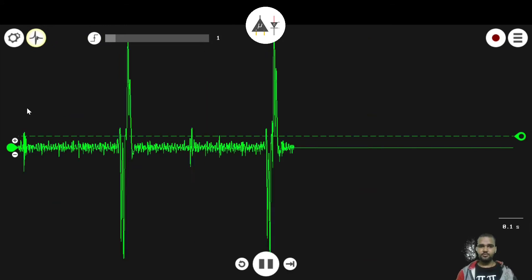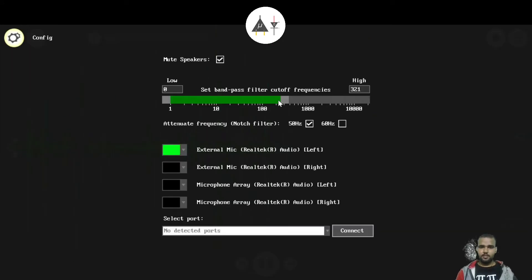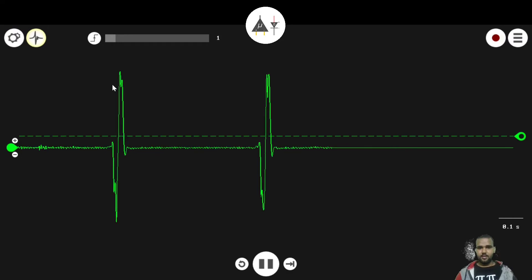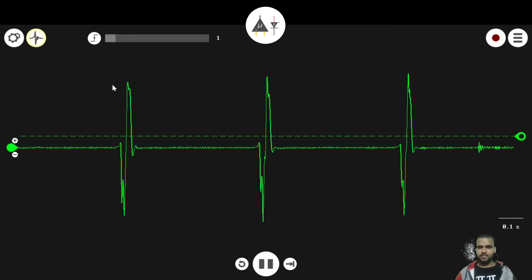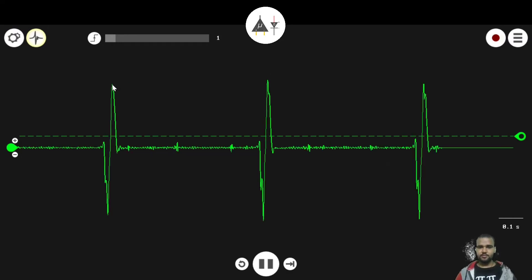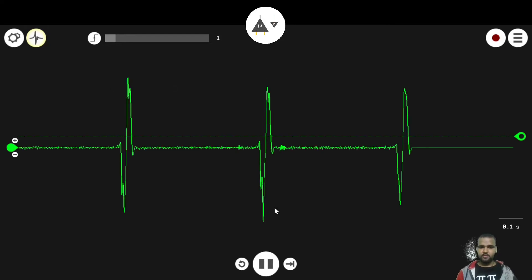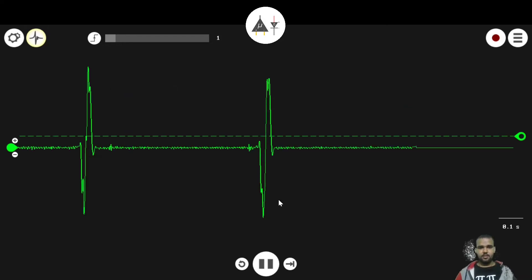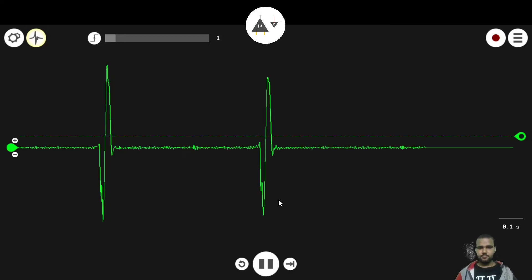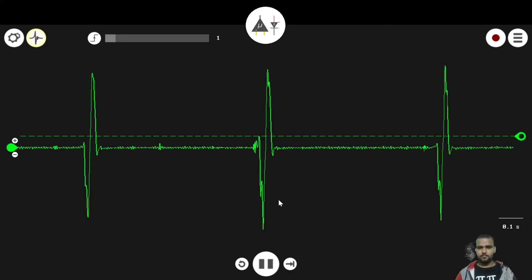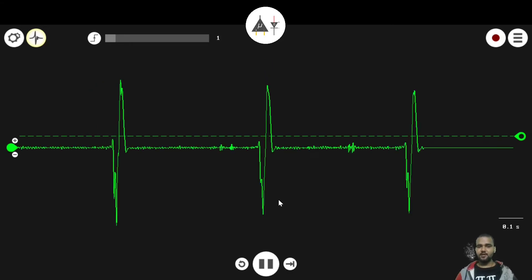You can see some EMG artifacts when I breathe. Let's try to change the frequency band. I will make 0 to 67. The ECG signal is much cleaner now and you can see all the peaks, PQRST. This is much more like an ECG now.